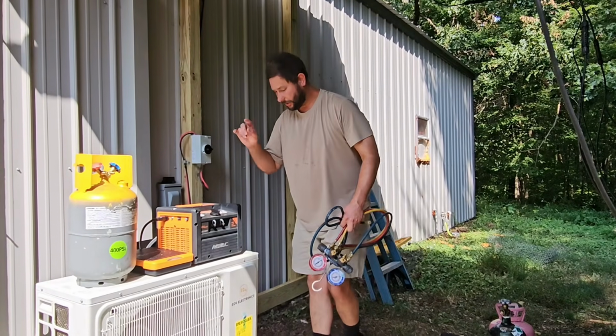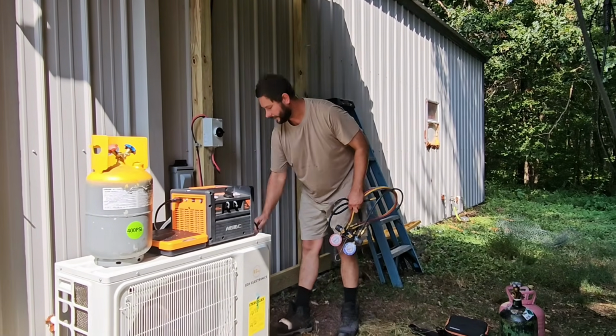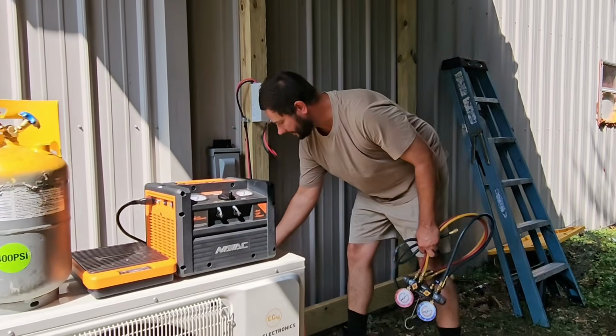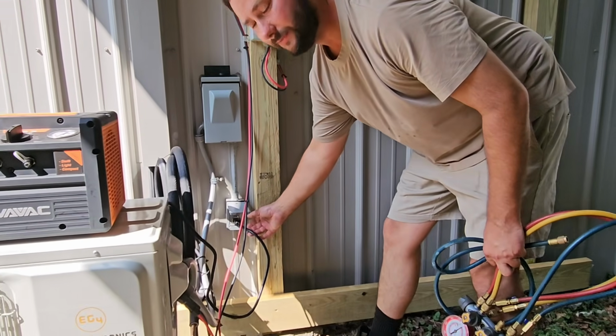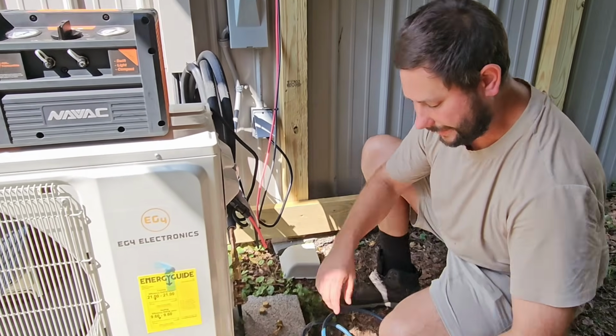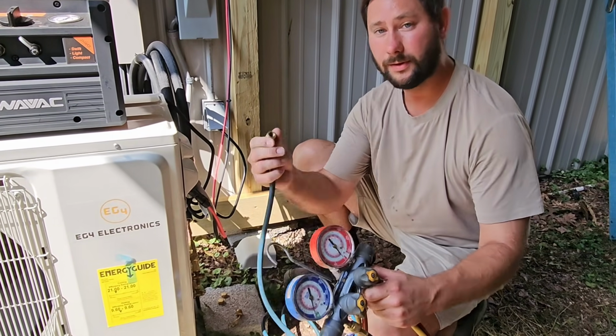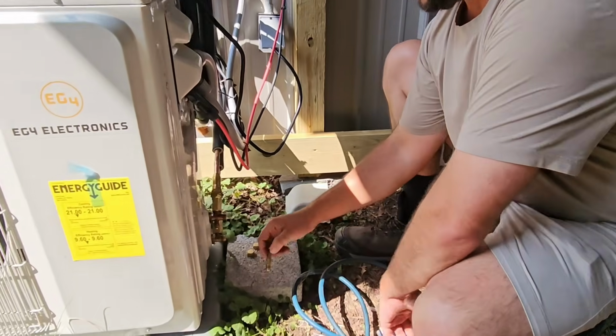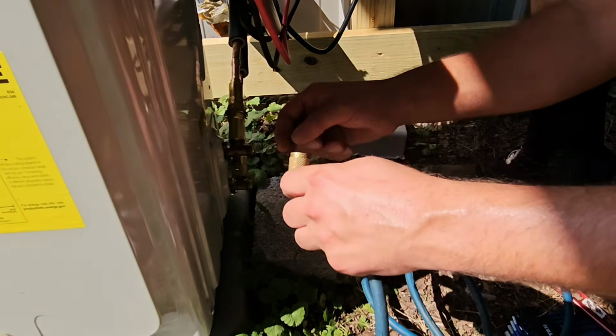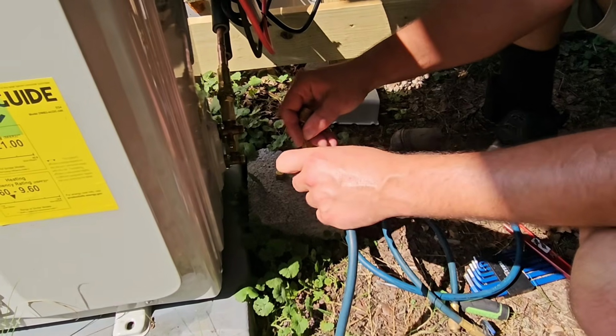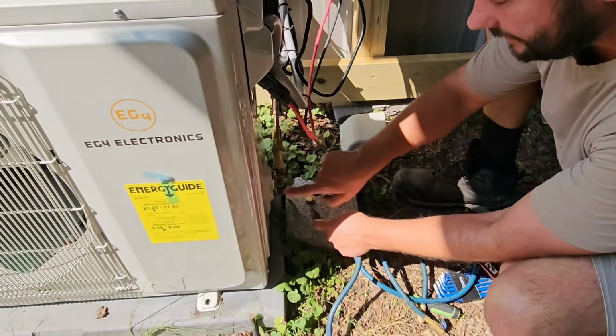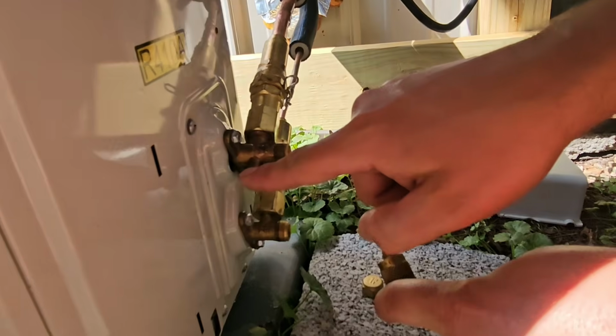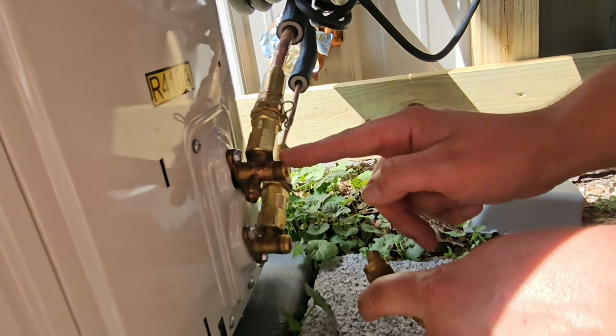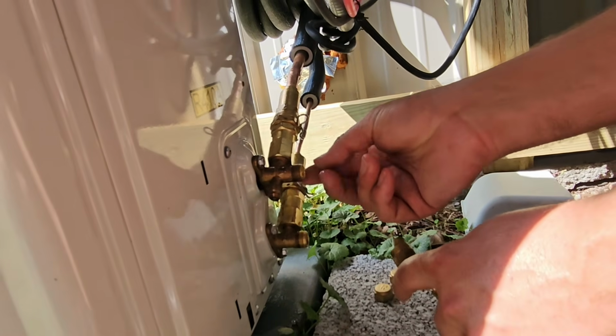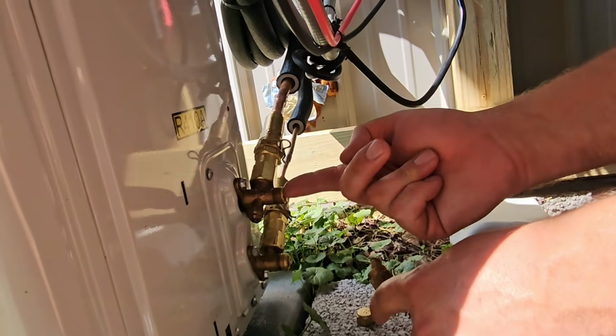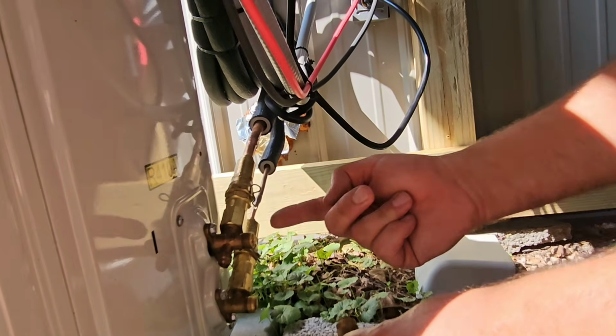So first thing we're going to do to hook up the recovery machine is plug it in. It's a 110 volt plug, and I've got it plugged into this 110 volt receptacle. Now we're going to take our gauges, and I'm going to be using my blue hose, and I'm going to hook it to my adapter. Here's my 1/4 inch to 5/16 adapter, and I've already got the cap off. This is my service access fitting connected to my suction line service valve. This is the larger valve on the mini split, and this is known as the suction line or the hot gas line during the heating mode.